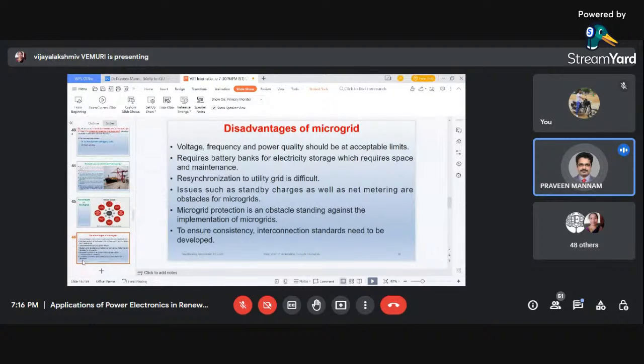Resynchronization to the utility grid. When you observe the microgrid, it has different operating modes, as I explained before: on-grid mode and off-grid mode. In on-grid mode, this microgrid needs to connect to the conventional grid, but it must be synchronized correctly. If it is not done correctly, there is a problem of stability. So resynchronization to the utility grid is very difficult. That is the third drawback.